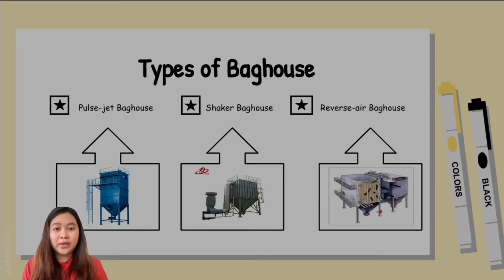Cement manufacturing companies rely largely on dust collectors, which are present in large numbers. Auto, Walter, and Darrell studied the pollution control system operating the clinker coolers on the two largest kilns, which produce 40% of the clinker. From the studies, they chose the pulse-type baghouse after considering all characteristics, including temperature, dust resistivity, dust load, volume variation, horsepower, maintenance expenses, and overall efficiency.